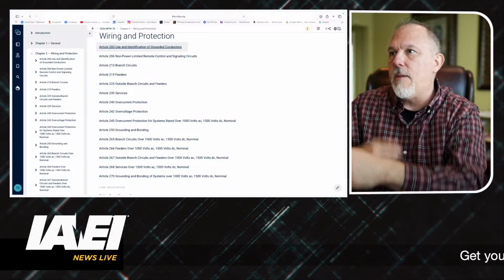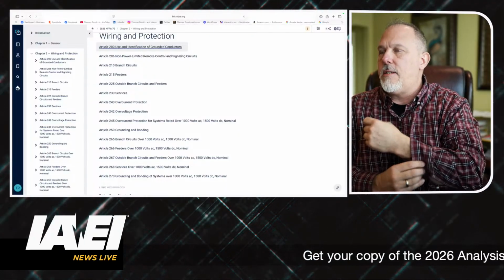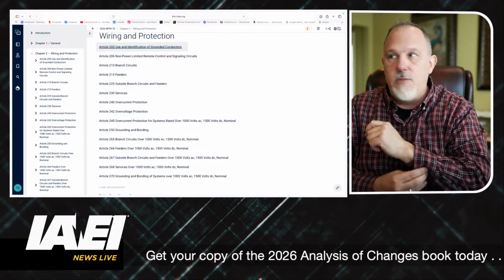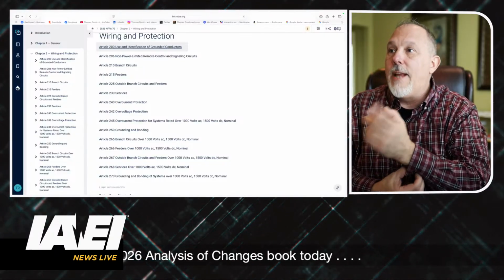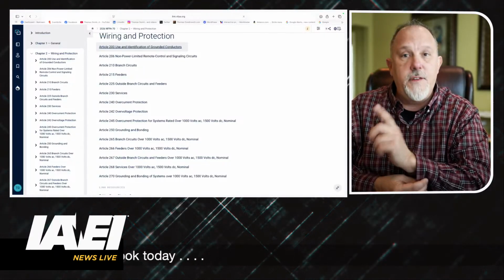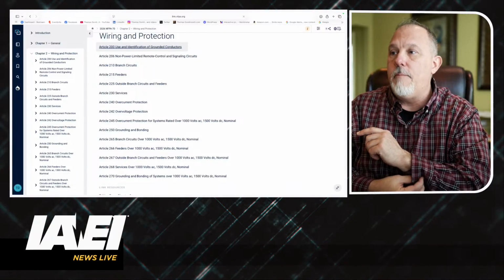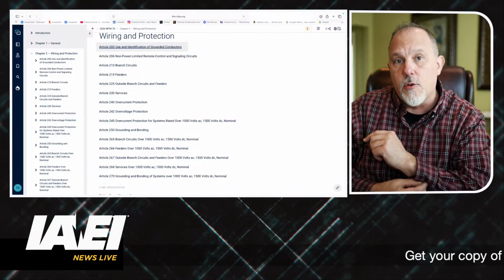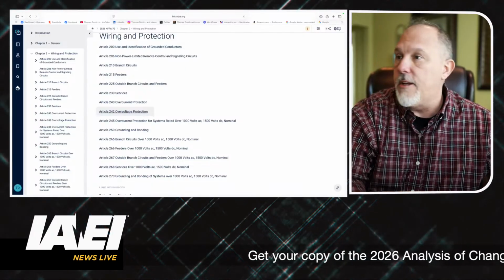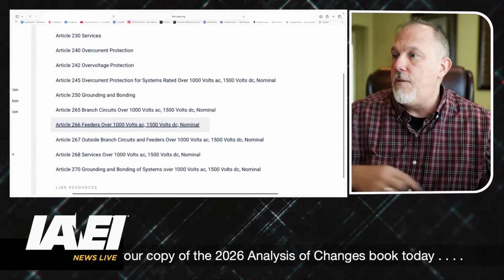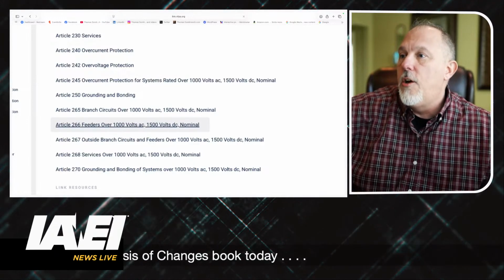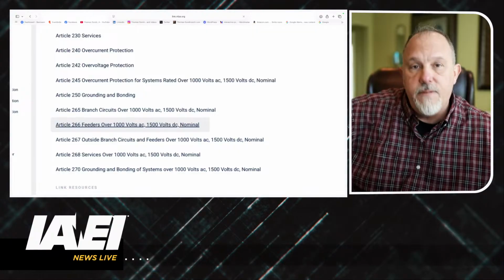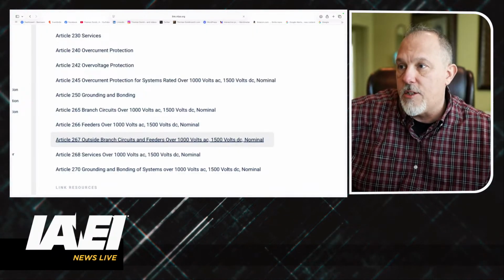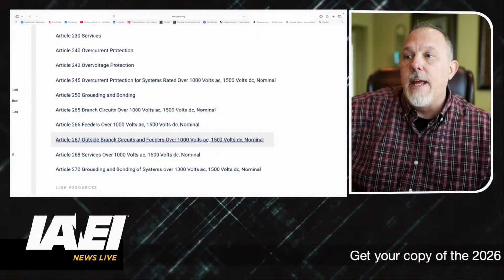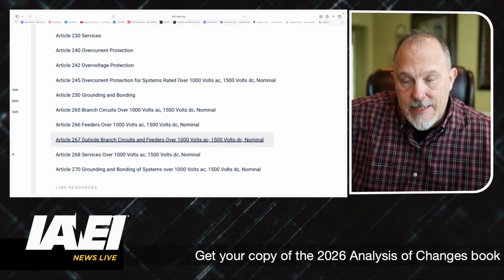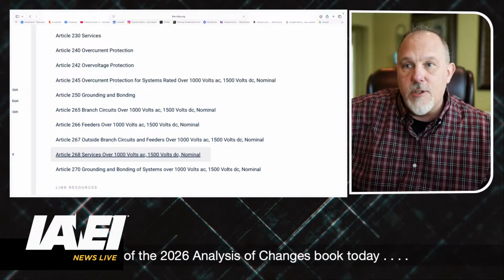Article 206, non-power limited remote control and signaling circuits. We've got branch circuits in 210, 215 is feeders. Now, keep in mind that 215 is feeders, but it's not medium voltage feeders because that is Article 266. So what you're going to notice in here is that you've got Article 266 for feeders over 1,000 volts AC, 1,500 volts DC. We've got outside branch circuits and feeders over 1,000 volts AC and 1,500 volts DC. That's in 267. Then you have 268, which is services.